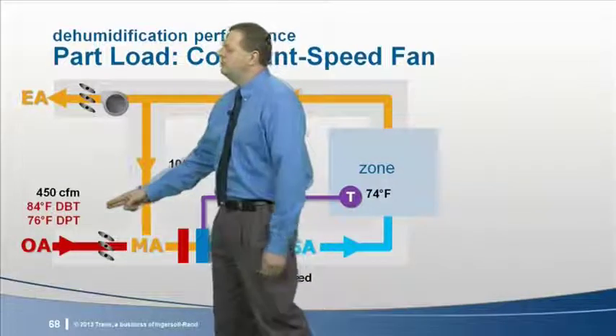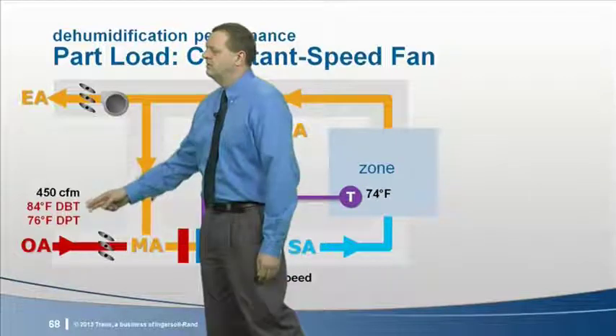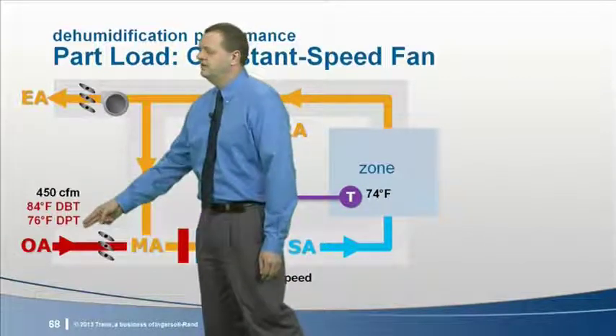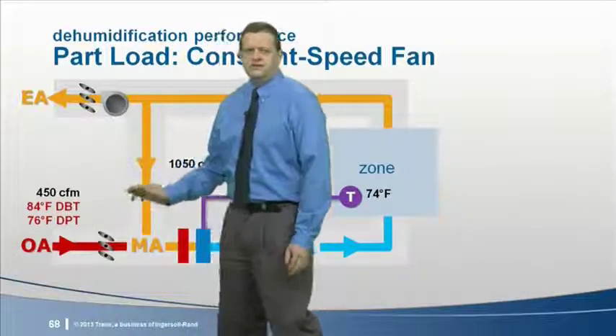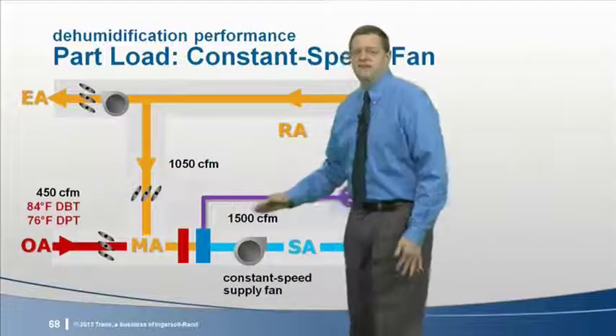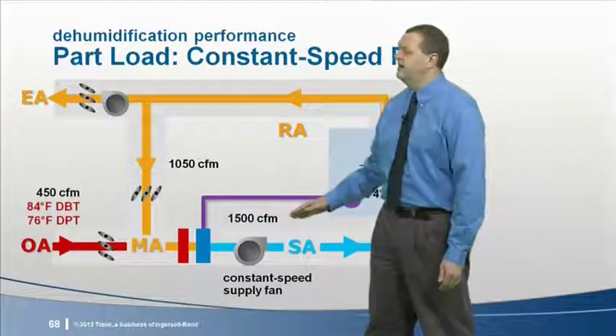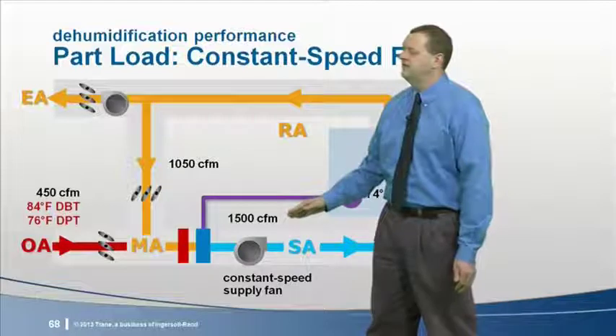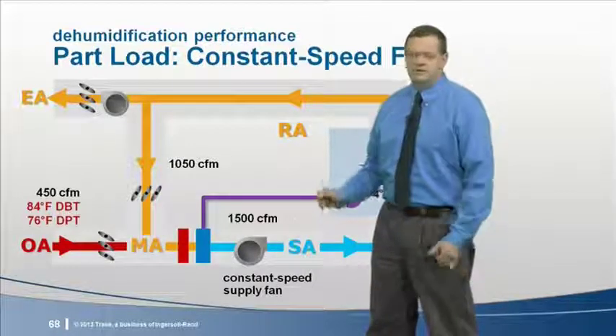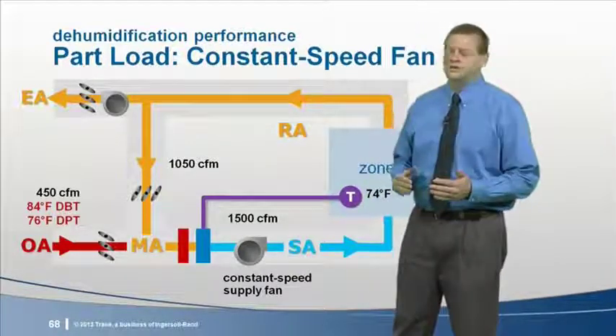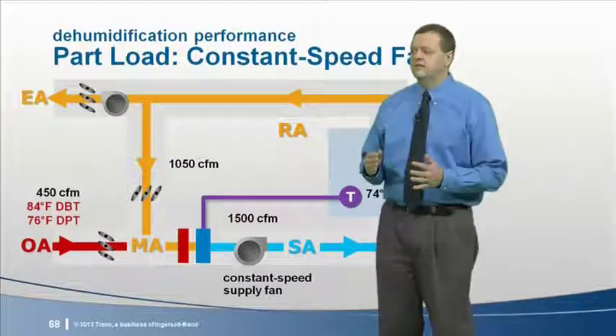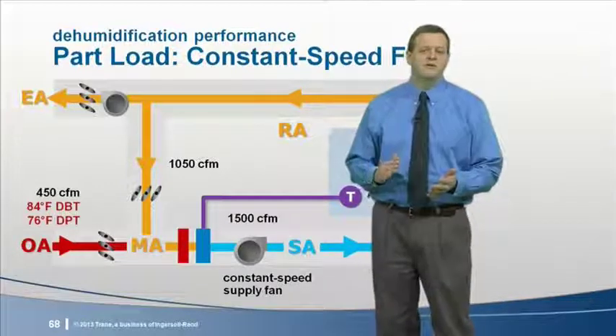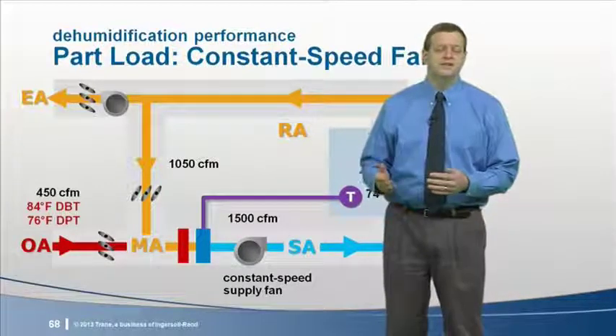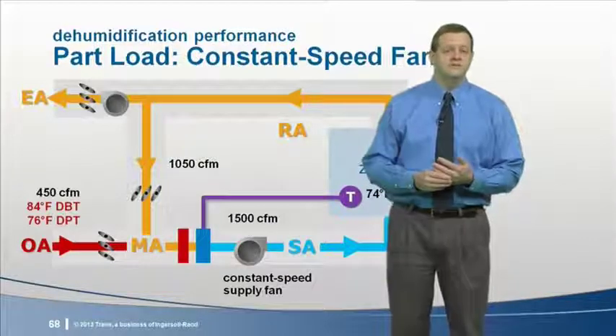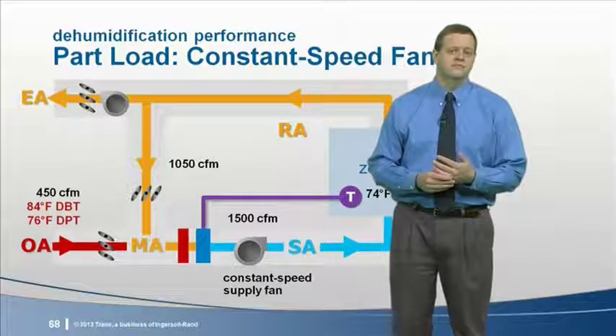This is the peak dew point condition for Jacksonville, when it's not as hot outside, but it's more humid. This system, with a constant speed fan, continues to supply air at a constant volume, 1,500 CFM in this case. Meanwhile, as the sensible cooling load in the zone decreases, the compressor cycles on and off, resulting in warmer air delivered to the zone, 63 degrees for this example load condition.